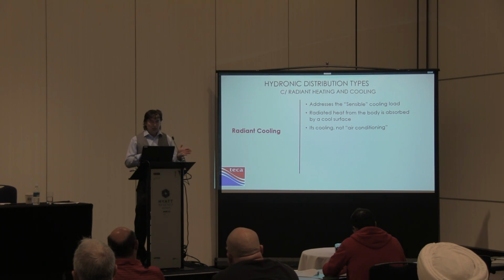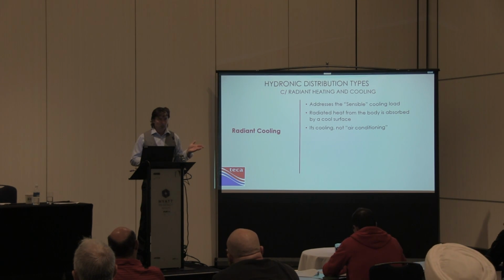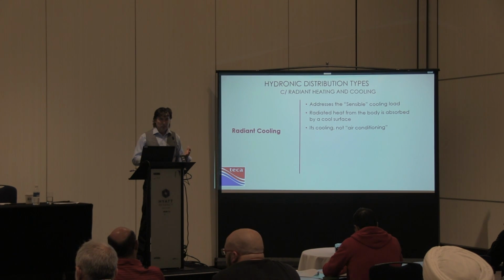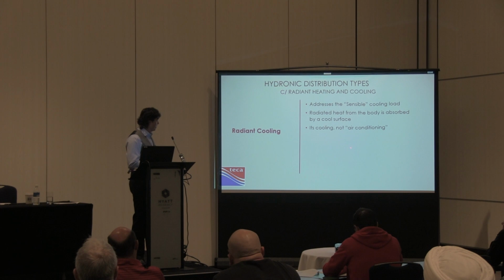So if that's what you're trying to get rid of, and if we think about it, in a home, what is our air conditioning load? A sensible load. If you got the solarium, you're going to have sun shining in there. That's going to be a sensible load. But once the place is sealed up, you're cooking in there, you're doing laundry and so forth. We do have a latent load. People are a latent load. So there's a latent requirement to make that air conditioned.